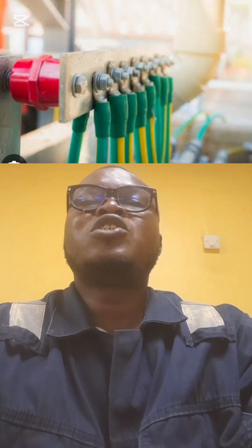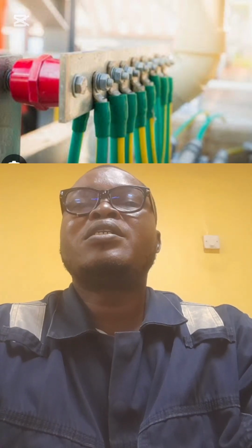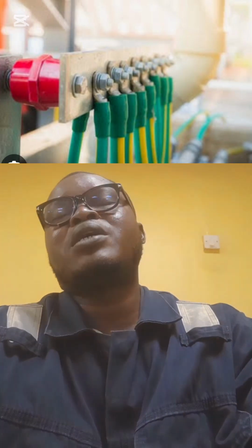Then approved tools and PPE must be mandatory anytime we are performing an intervention on any electrical device or equipment. Apart from that, in considering electrical safety with regard to protection, we also have to note that earthing and lightning protection are very important. Protective earthing is connecting an exposed conductive part to earth, giving a fault current a low impedance path to the earth protection quickly.